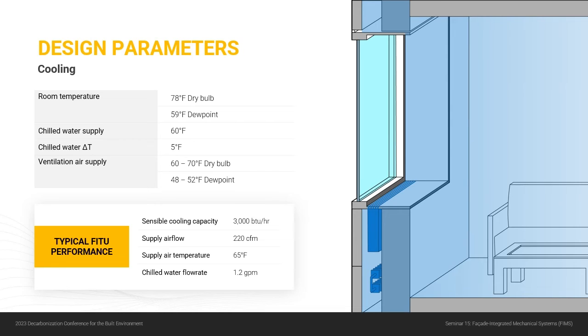Now the FITU, with a 6-inch depth, the units that we've built are getting roughly 3,000 BTU sensible capacity, which, as I showed before, is plenty for most rooms. But if you have, say, a larger living room, maybe it's a corner unit, you have a lot of windows, so you have a higher load, then you can just use more than one FITU to meet your load.